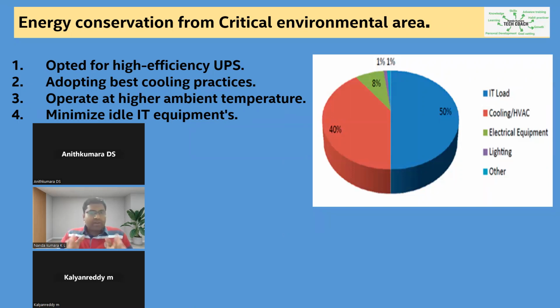Again, realignment of the precision air conditioning units. The air conditioning unit should be exactly on the hot air path, so that cold air goes to the cold air section and hot air can come back immediately to the equipment, and a faster cooling cycle can happen, so that it reduces the airflow losses as well. Realignment of equipment, proper containment, and blanking panels, that is also one of the important points.